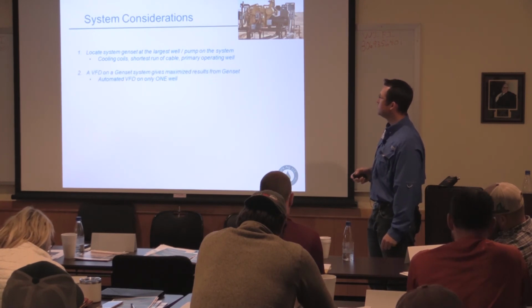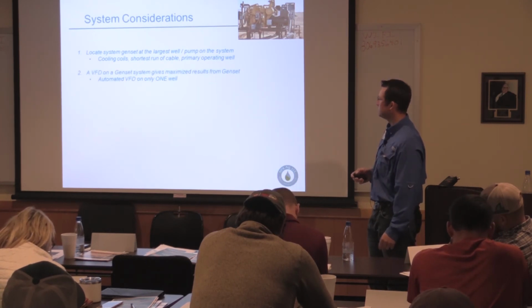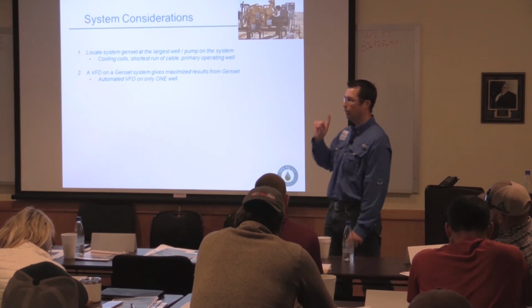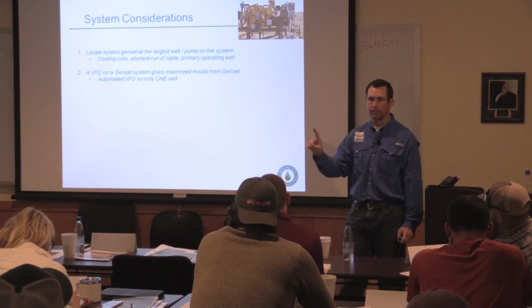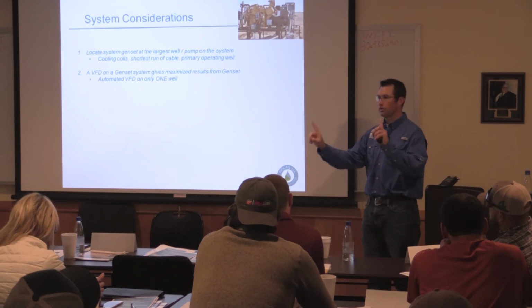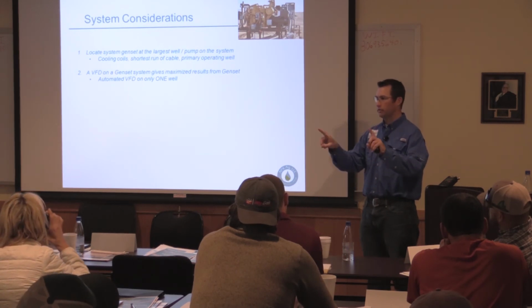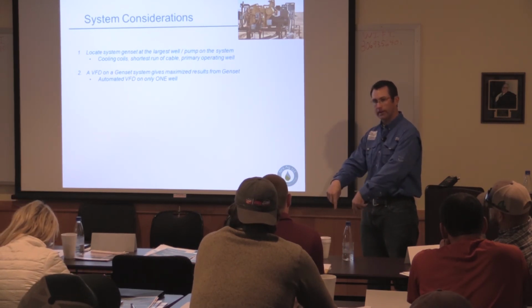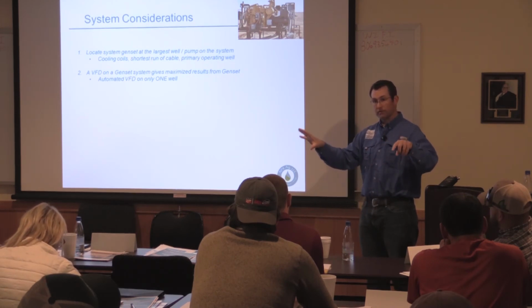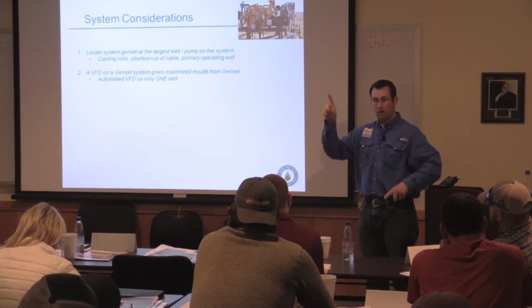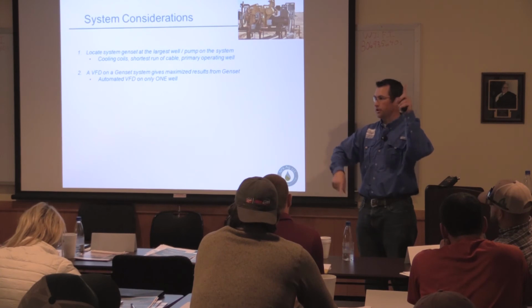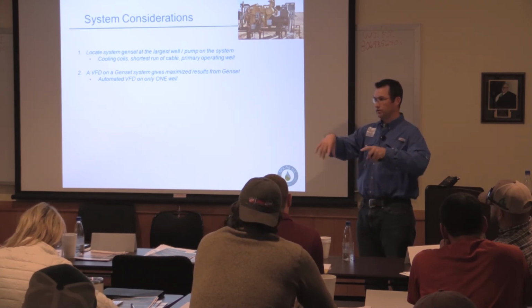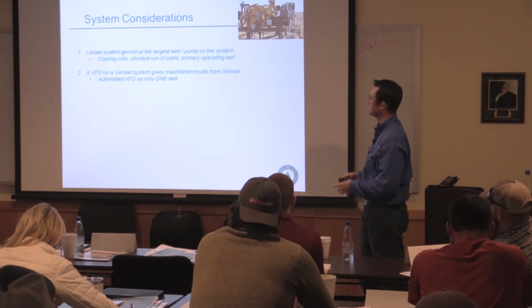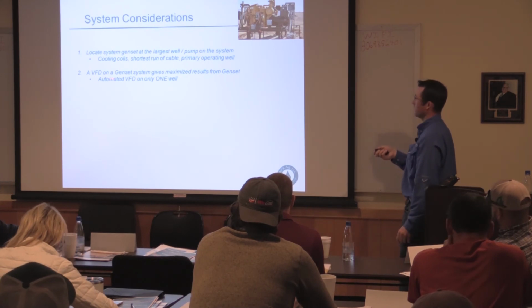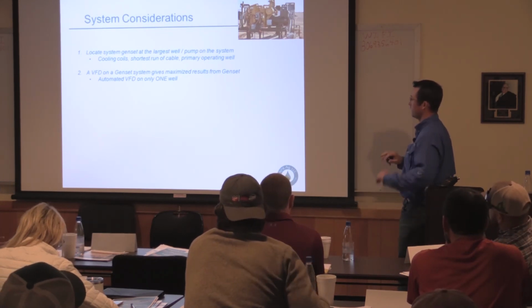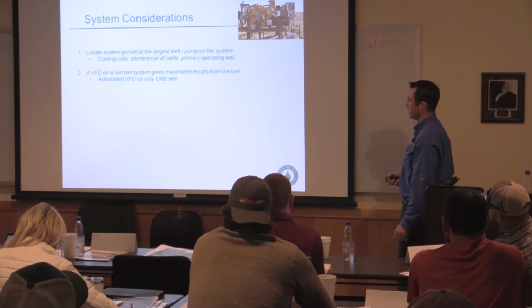And if you're going to automate VFDs, you want to be careful to only have one automated VFD on at a time. They can start to fight each other if you're not careful. If you automate them downhole and they're isolated, that's one thing, but if you automate them based on a pivot pressure or a line pressure, those VFDs will dance with each other and you'll never get it to line out. So if you've got multiple wells, make that consideration. I would recommend a VFD as part of the complete system of the genset. It is very helpful.